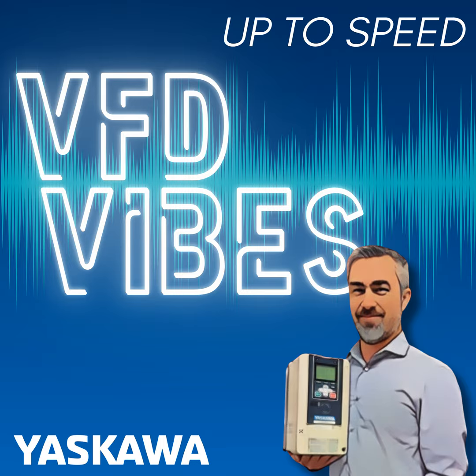So I understand, when you talked about trade-offs of every system, to then have to go and track that down at a large facility. Well, engineering is the art of deciding what problems you're willing to live with. People that have high resistance ground type installations, and these, by the way, are growing in popularity because of the arc flash issues and the arcing ground faults and things like that. More and more facilities are installing high resistance grounding.